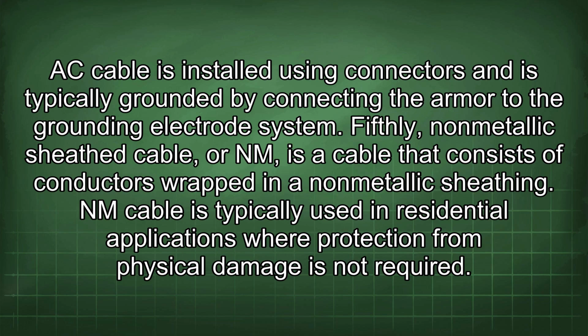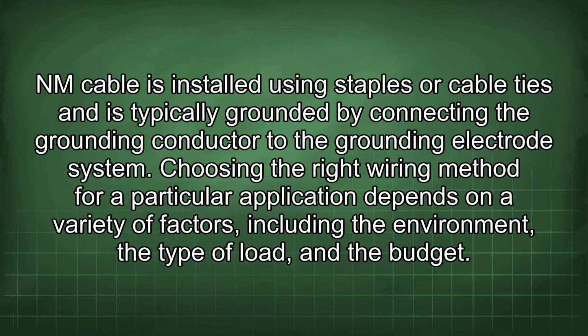Fifthly, non-metallic sheath cable, or NM, is a cable that consists of conductors wrapped in a non-metallic sheathing. NM cable is typically used in residential applications where protection from physical damage is not required. NM cable is installed using staples or cable ties and is typically grounded by connecting the grounding conductor to the grounding electrode system.